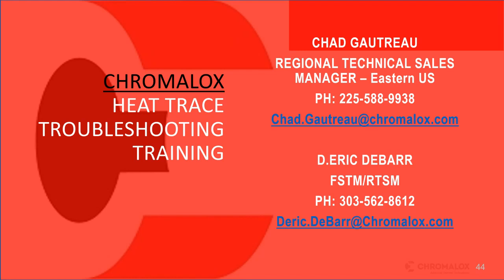Okay, fair enough. Back to the wireless RTDs, is there any distance or length from the controller, or will we probably have to go through the I&M on that? Yeah, that would be something we may have to address afterwards. I'm not sure what the distances are on those. We do have repeaters that you can install if you are at longer distances, or if you don't have a direct line of sight between the RTD and the controller. Okay.